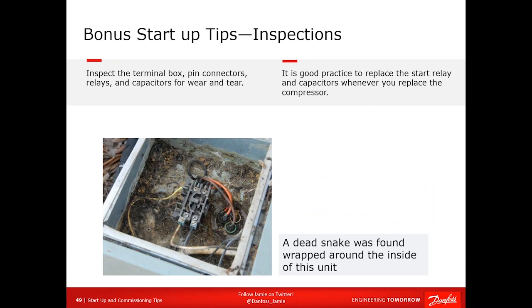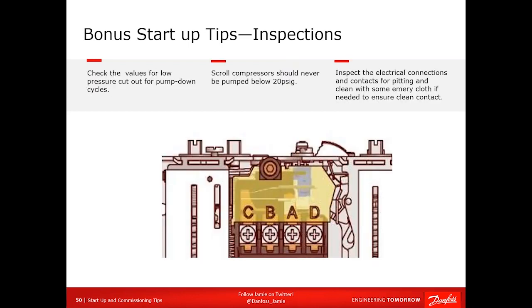In this case here, we had a dead snake in here. You'd be surprised what you'll find living or dead in here, all right? We pulled the relay out, the contactor, the capacitor, we cut back the wires and replaced them, replaced all this stuff because it's cheap insurance, all right? At least test it if nothing else. It's just good practice in ensuring that this is going to continue to run down the road.